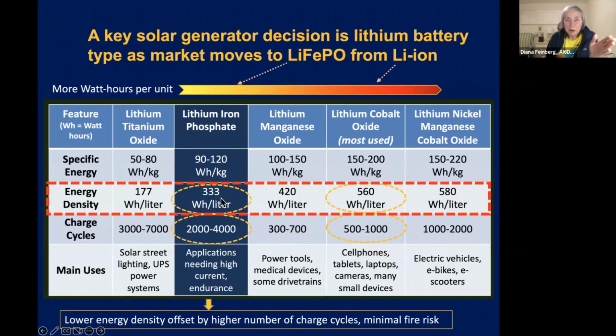The lithium iron phosphate battery generally won't catch fire. Everything in the world will catch fire at some temperature. In the case of lithium iron phosphate, these batteries will have thermal runaway typically at about 450 to 500 degrees Fahrenheit, whereas the lithium nickel manganese cobalt oxide batteries have thermal runaway at about 310 degrees.